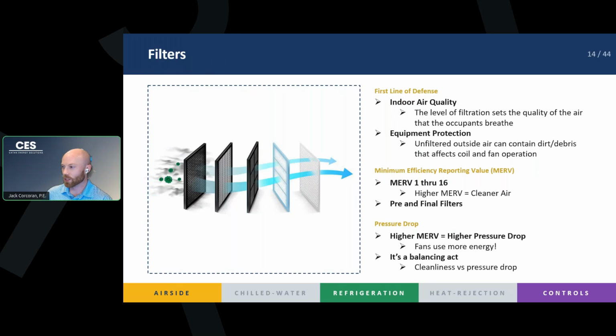But the reason you switch them out at all, I mean, if you wanted to get rid of all that dirt and debris, right, to have a clean unit. But the more dirt and debris that gets caught, the higher the pressure drop, right? Your fan is going to be using more energy. You're going to be working twice as hard if you have all that gunked up dirt and debris in your filters. So you want to replace them pretty often so you don't have that high pressure drop through the filters.